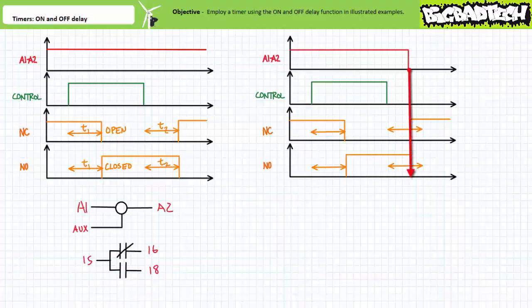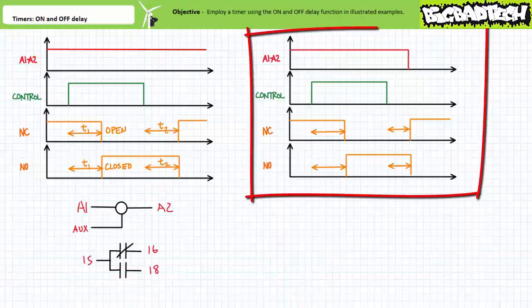power to the coil during the off delay period, the timer would halt the delay and immediately return the contacts to their deactivated state and reset the timer. This allows an on and off delay timer conducting the off delay to be overridden by an emergency input for immediate stop purposes. A modified timing diagram illustrating this act appears here. We'll examine this feature in a moment.